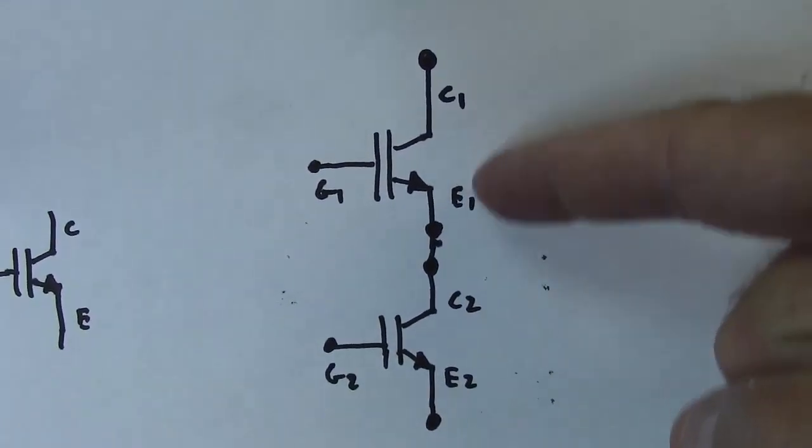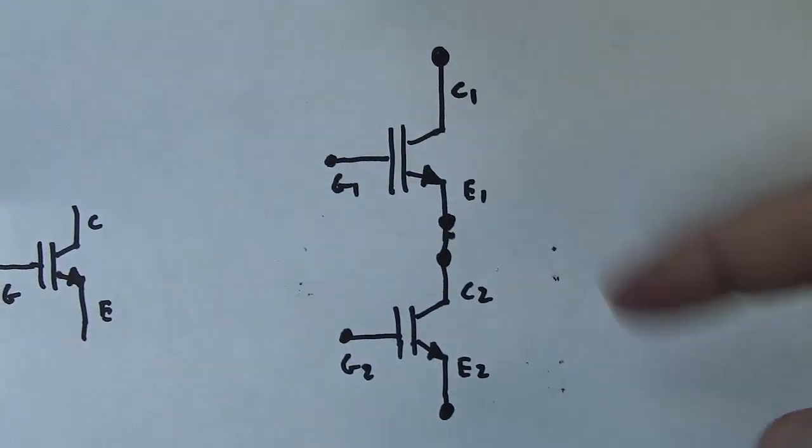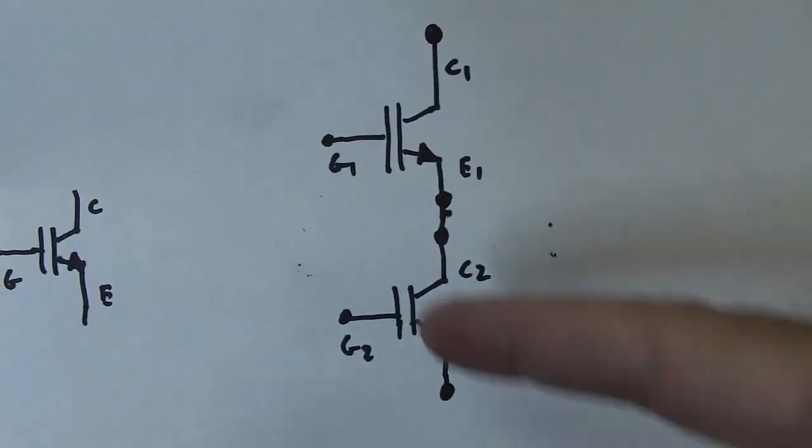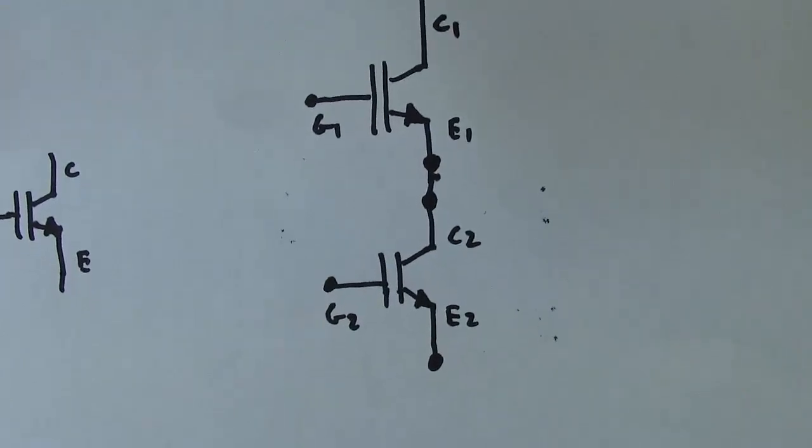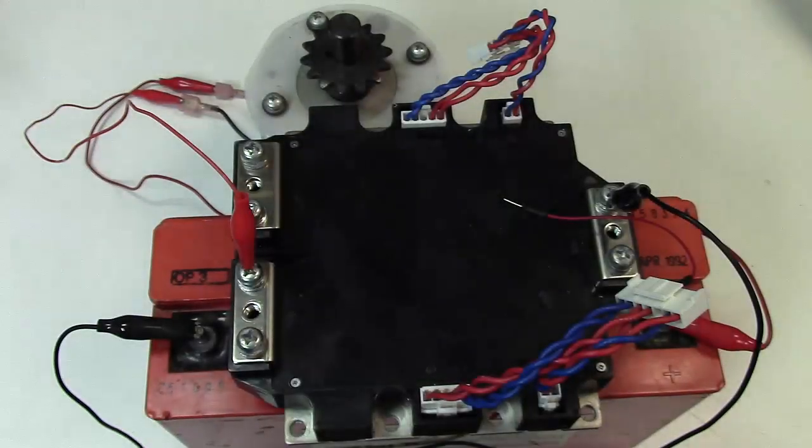So this is testing the top IGBT. So we've already verified by doing this that this IGBT, E1, C1, and G1 are okay. Now we're going to shift and check the second IGBT in the brick.